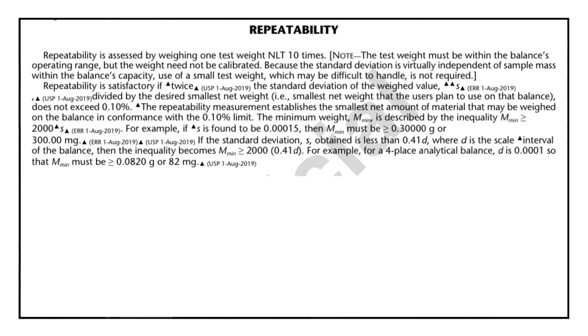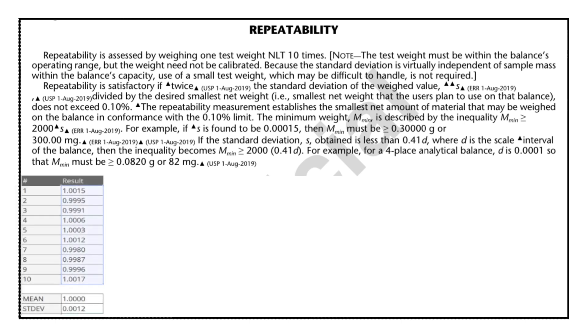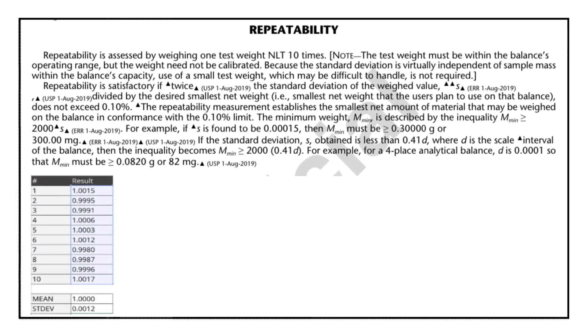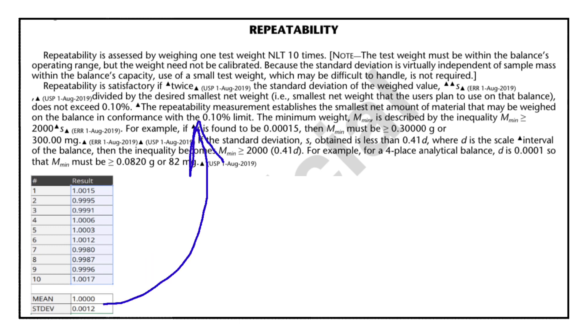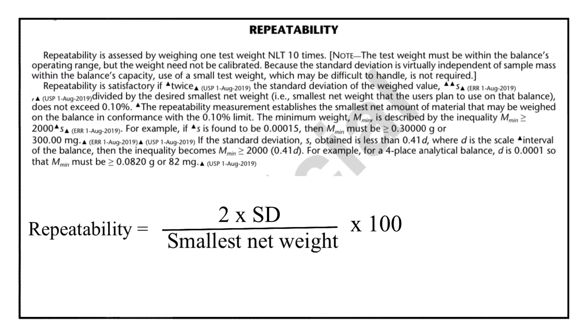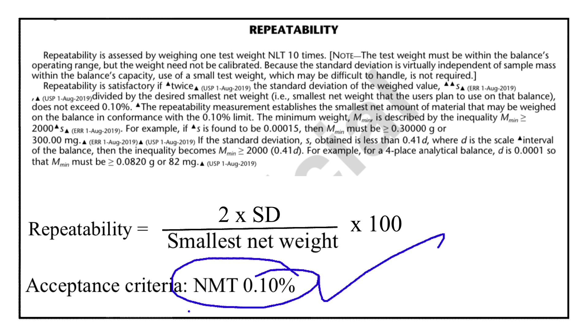Now let us see how these test parameters are performed. To perform the repeatability test, a single test weight is selected and it is weighed again and again for 10 times. The standard deviation is calculated for these 10 weights, and the obtained standard deviation value is entered in this formula to get the repeatability result. The formula is: 2 × standard deviation ÷ smallest net weight × 100. The obtained value should not be more than 0.10 percent.